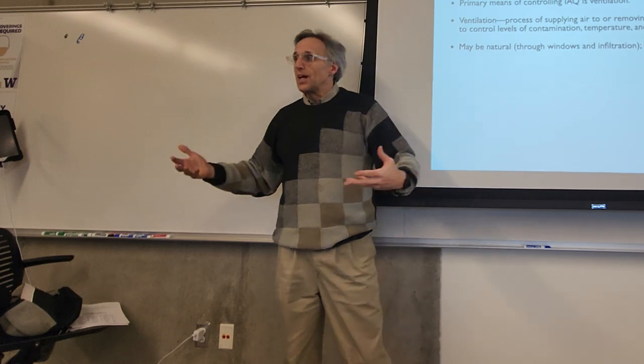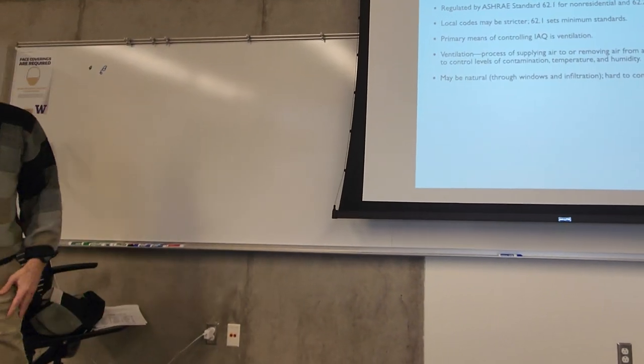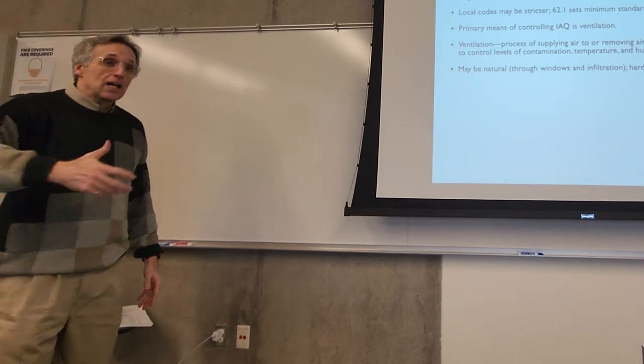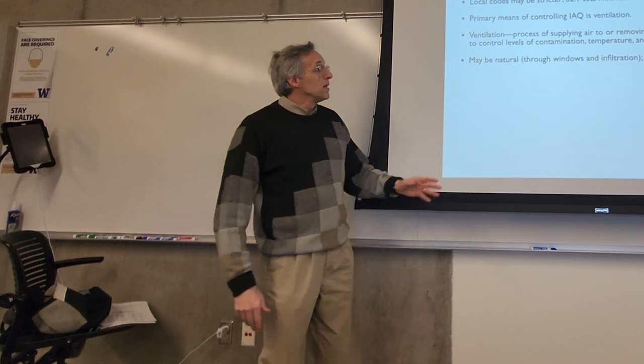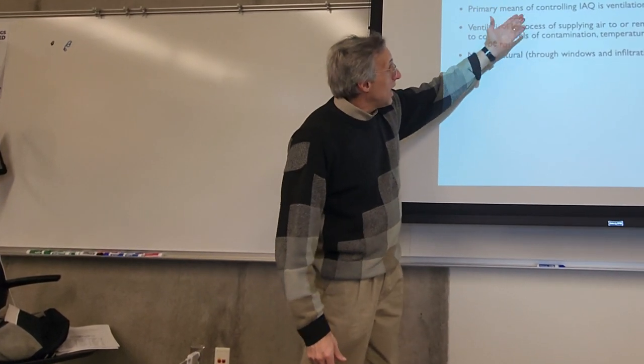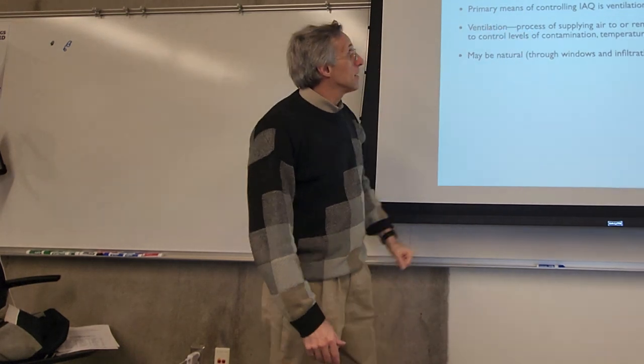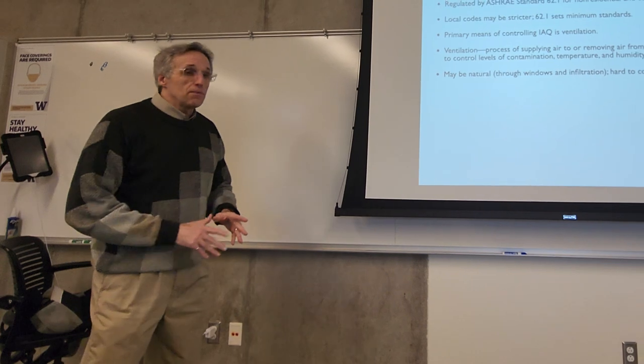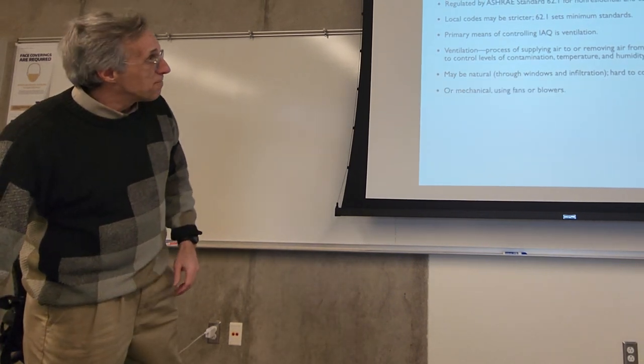Return air is already at 70 degrees. It doesn't take a lot to bring that back down to 55, 60 degrees. But if it's 95 degrees outside and you're having to bring in a lot of outside air, that's costly. The minimum quantity we have to have is set by Standard 62, and then local building codes will even be stricter in some cases than that.